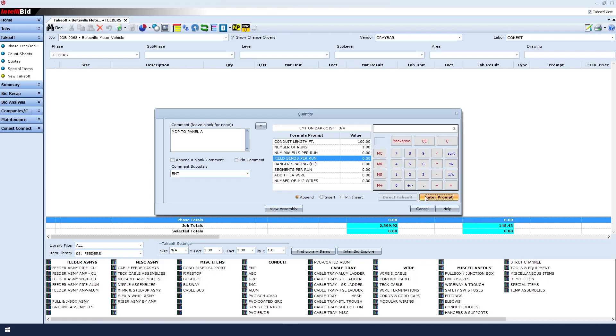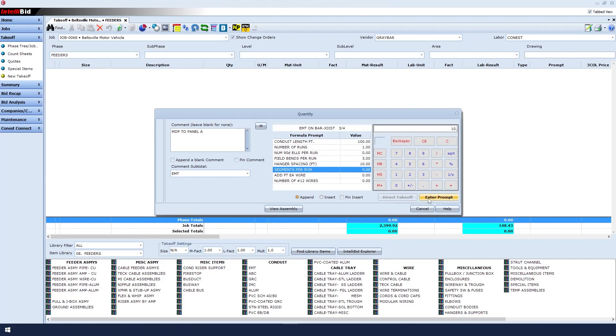For hanger spacing, let's put 10 feet. Enter Prompt. For segments per run, a segment is really trying to calculate how many connectors to give you. In order to know how many connectors to give you, you need to know how many boxes. So in this case, we'll say there's two boxes. Enter Prompt.